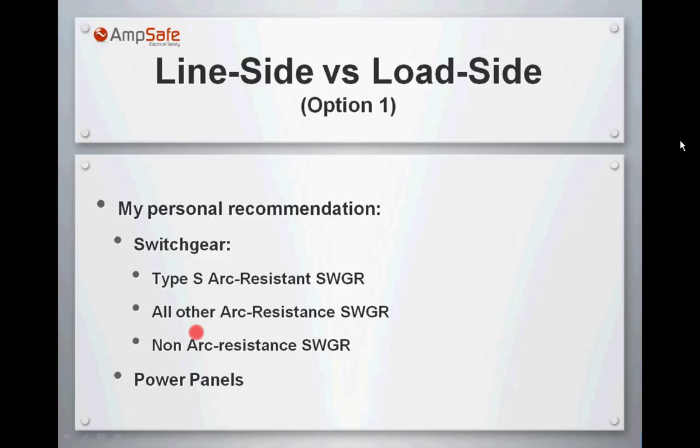That's very restrictive for the customer. The customer might be limited not to work on some panels because you have chosen this route, but it's the safest route, the one that gives you less risk and protects the employees more. But of course, it handcuffs a lot of the maintenance procedures. Okay? So this is what I do in all the switchgear.